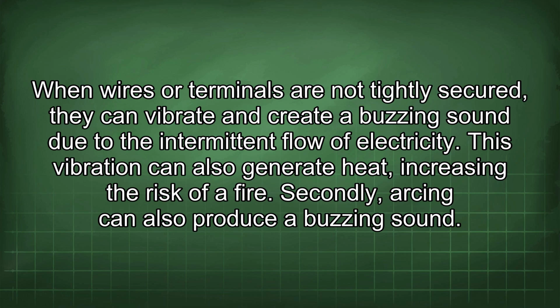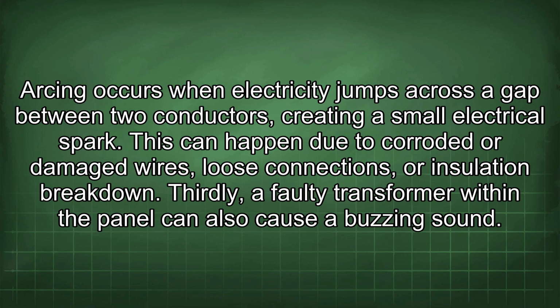Secondly, arcing can also produce a buzzing sound. Arcing occurs when electricity jumps across a gap between two conductors, creating a small electrical spark. This can happen due to corroded or damaged wires, loose connections, or insulation breakdown.